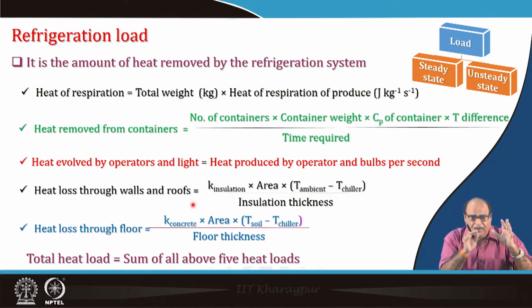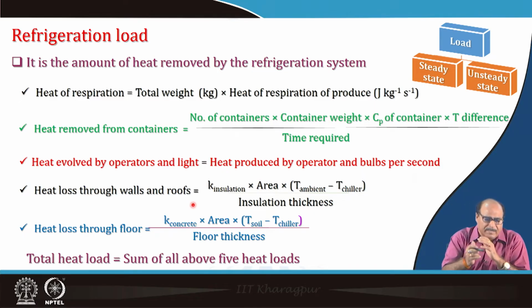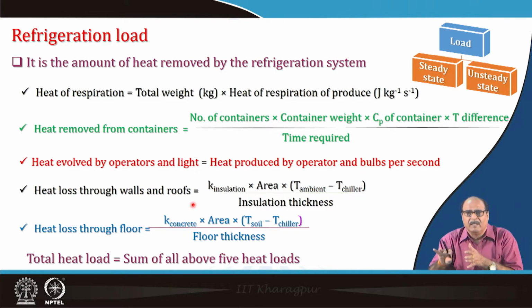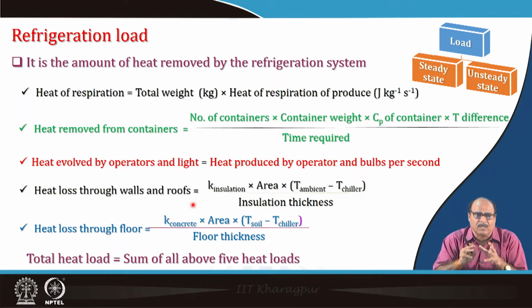So for keeping material in food for the required time, we normally calculate the refrigeration load of the storage. Refrigeration or cold storage load can be calculated by considering different heats, there are 5 types of heats. This refrigeration load is the amount of heat removed by the refrigeration system, and it is an important attribute while designing the cold storage facility. One must calculate what should be the refrigeration load of the system.